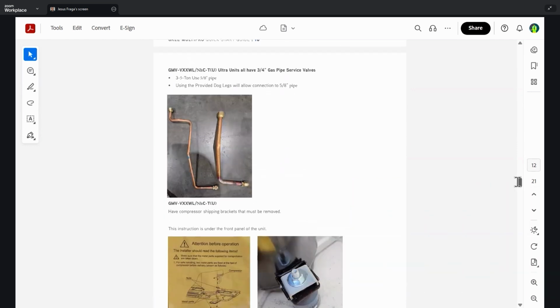So moving on here, these additional pieces, or dog legs as we like to call them, will allow you connection of a 5/8 pipe. So pretty much it's an extension of the service valves from the actual compressor service valves to the outside of the unit. So these will take you to the right-hand side, and it'll penetrate through the access hole and let you connect your line sets there. That way you're not having to use a ratchet bender or fittings to be able to get up there to the flared connections.